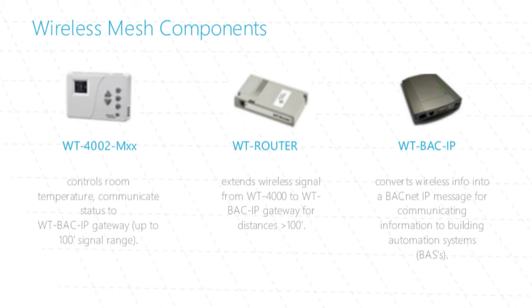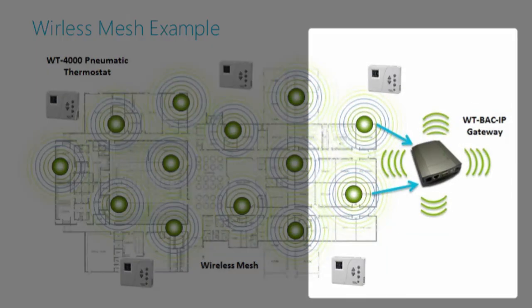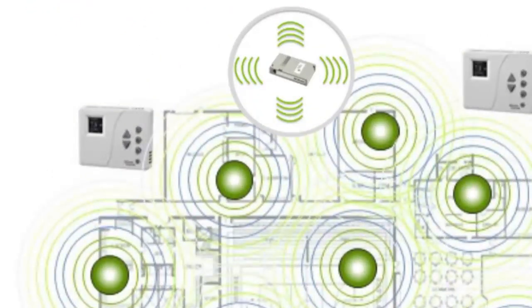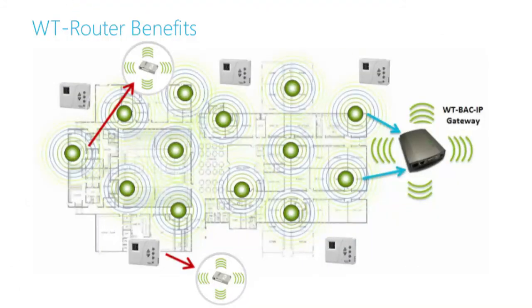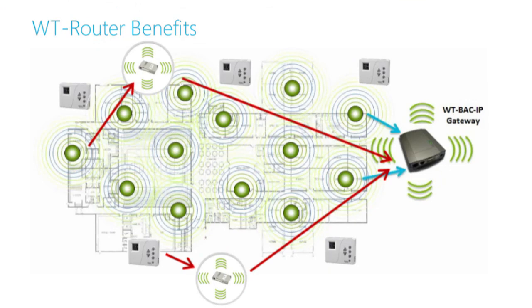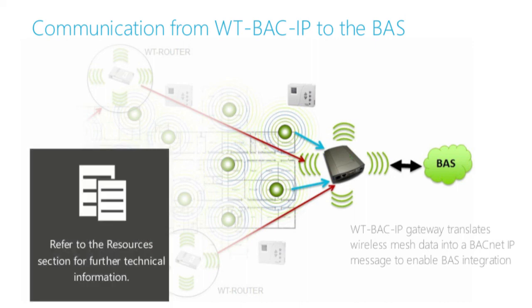WT-4000 series thermostats within 100 feet of the WT-BAC-IP gateway can send wireless data directly to it. WT routers can extend the range of thermostats located farther than 100 feet by offering an interim route of communication — thermostats send data to the routers, and the routers relay it to the WT-BAC-IP. These routers provide multiple routes of communication, ensuring data from each WT-4000 thermostat can complete its path. There, it gets translated into a BACnet IP message that enables integration with the Building Automation System (BAS).